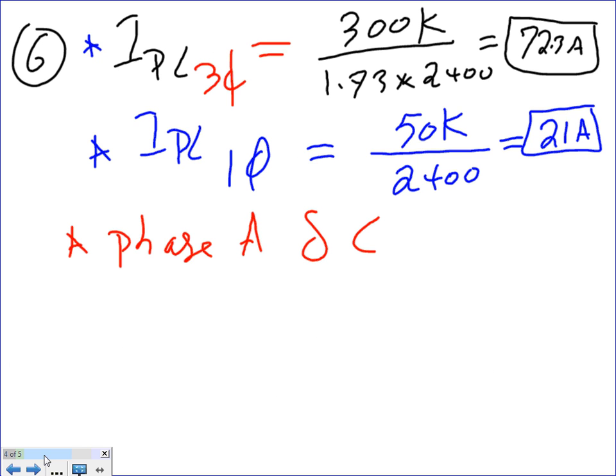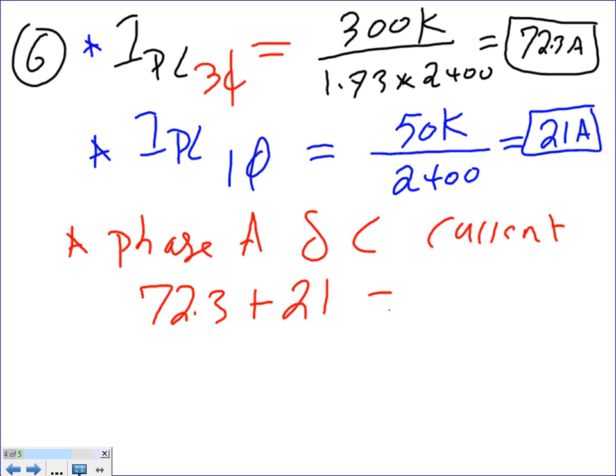What does that mean? If you come over here, for phase A and C, you just add the currents up. So phase A and C current, which is line current - you add 72.3 plus 21, that gives me 93.3 amps. Done.